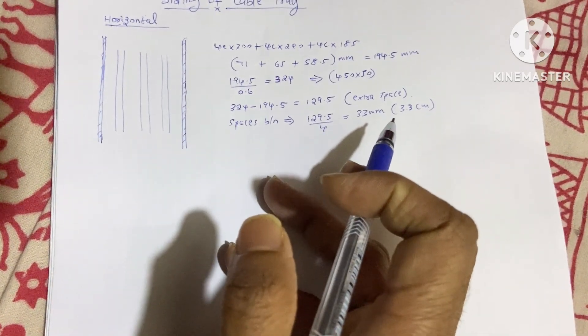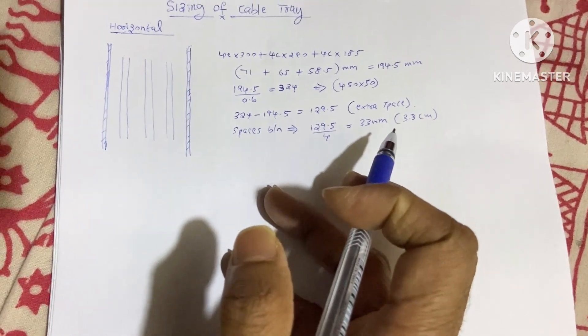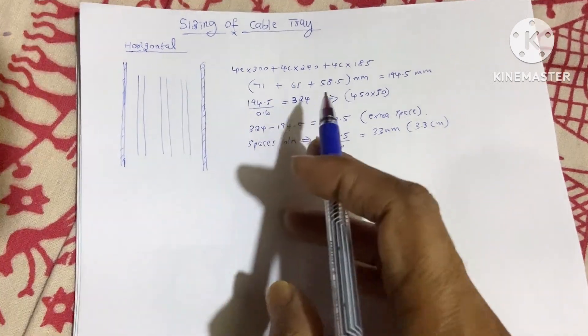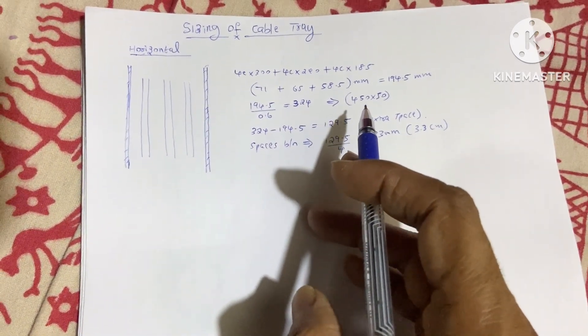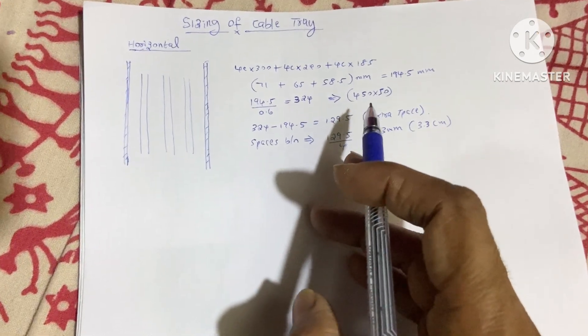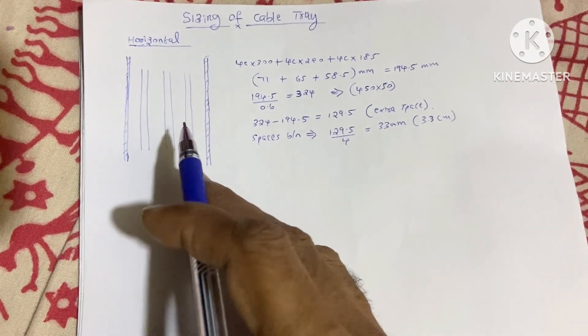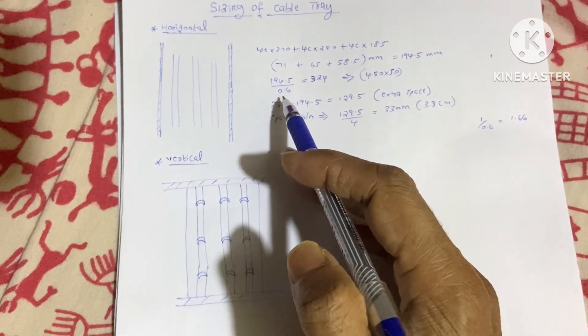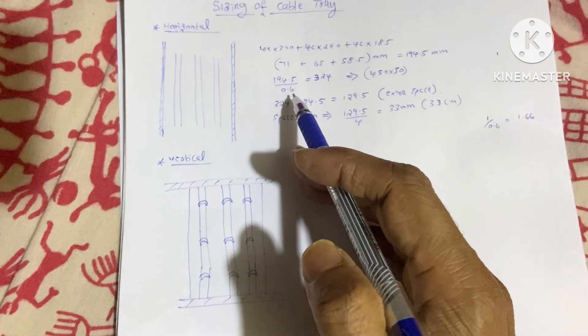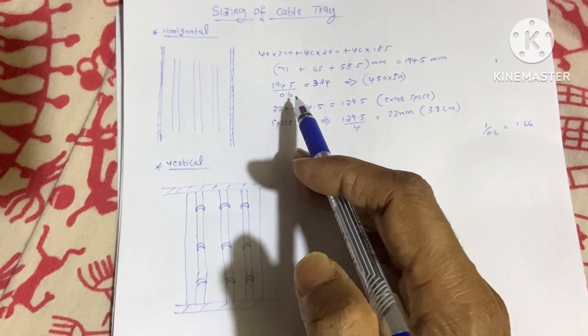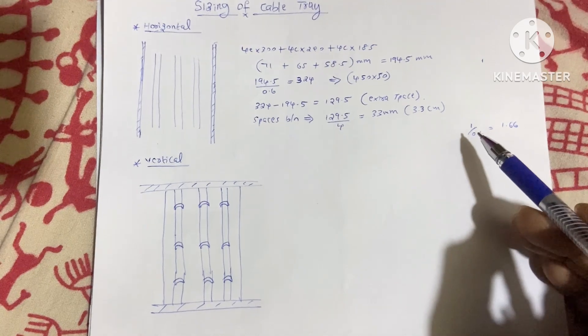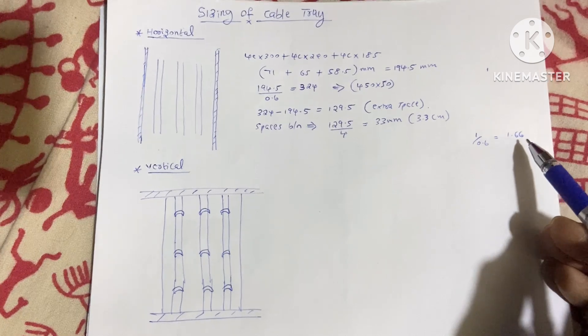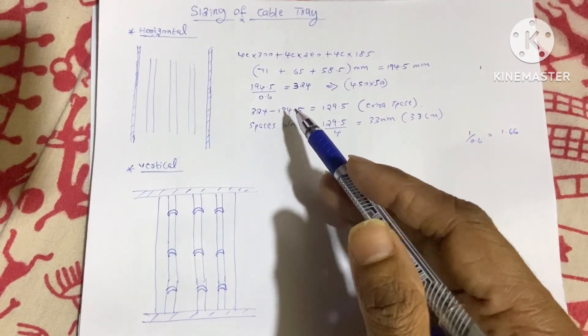We have taken a 0.6 safety factor for this calculation, which means we are dividing by 0.6, equivalent to multiplying by 1.66. This means we are giving 66% extra space for the horizontal cable tray calculation.